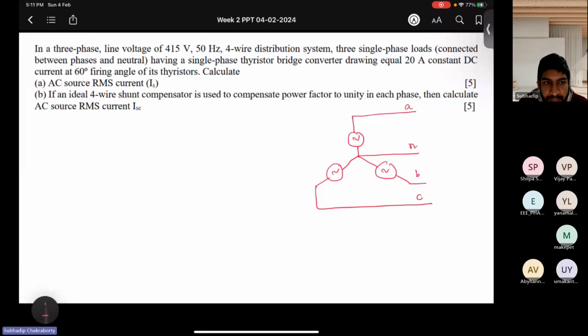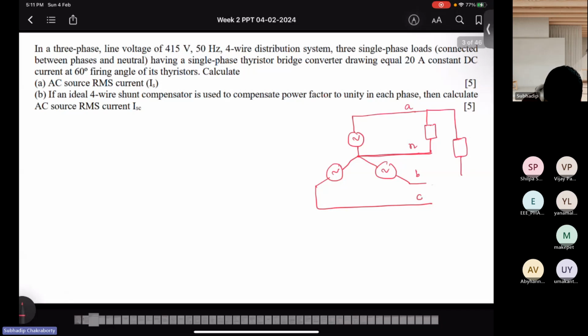By single phase loads, what do you mean? Please unmute, and any one of you can interact, because these sessions are designed for interaction and you can practice along with me. That will help you solve the assignment problems. So please be interactive. Single phase load means it is connected between a single phase and neutral. Every phase you have the live, and then the neutral is going to this fourth wire. Between phase A and N you have one load. Between phase B and N you have another load, and between phase C and N you have another set of loads.